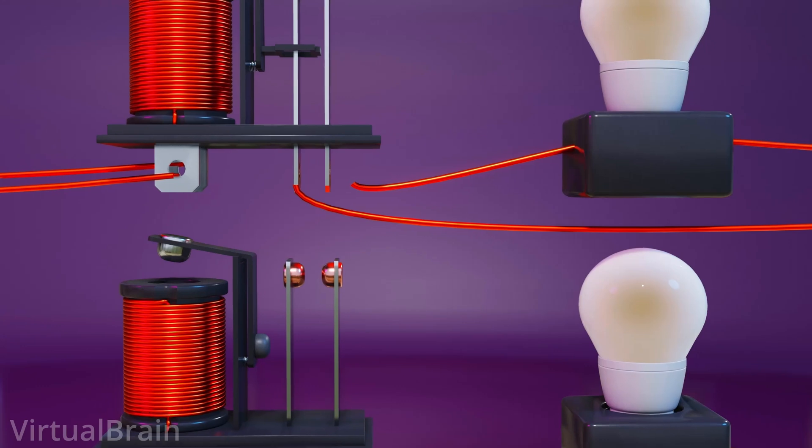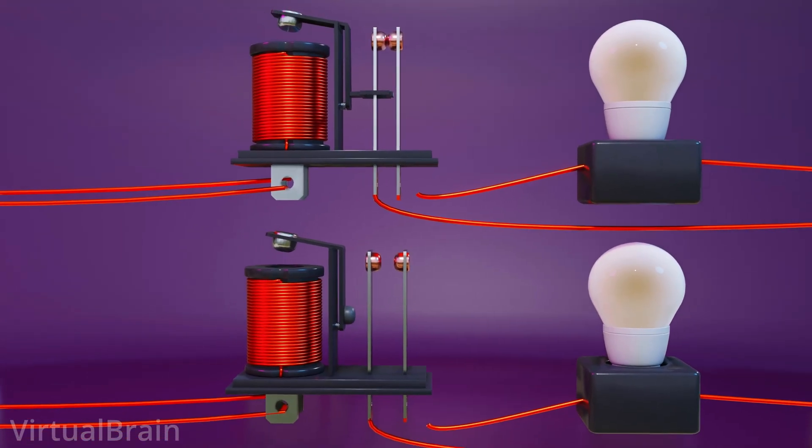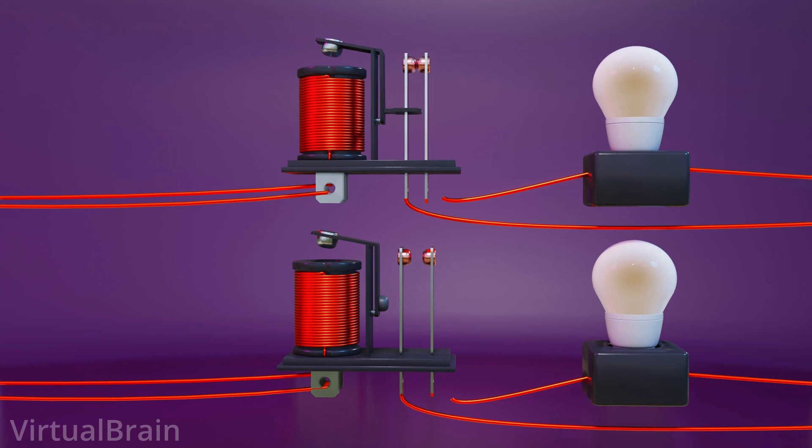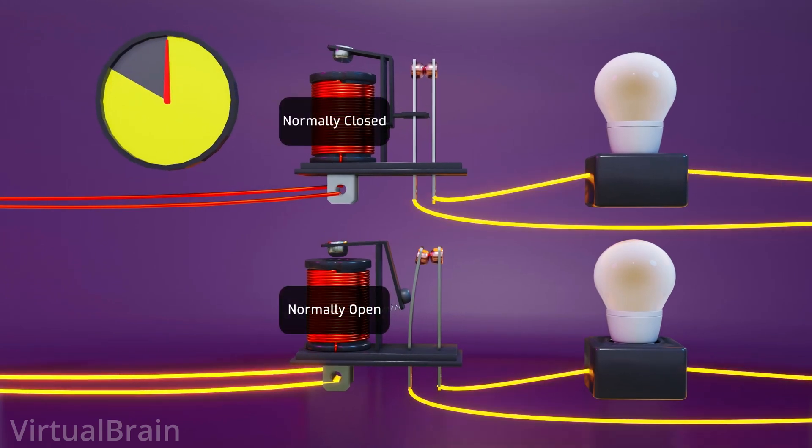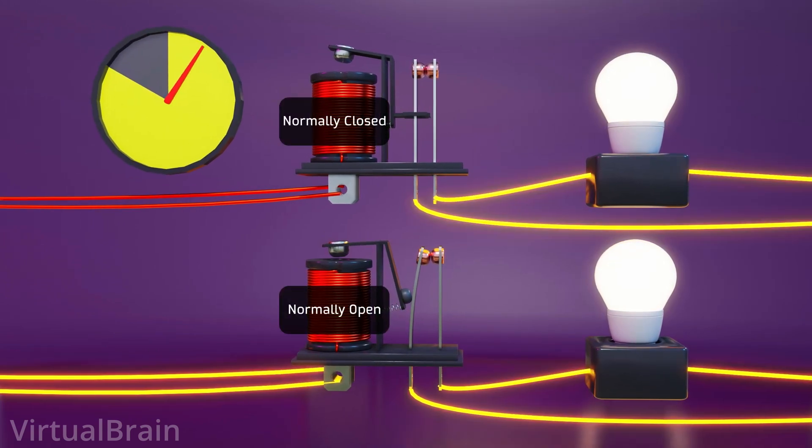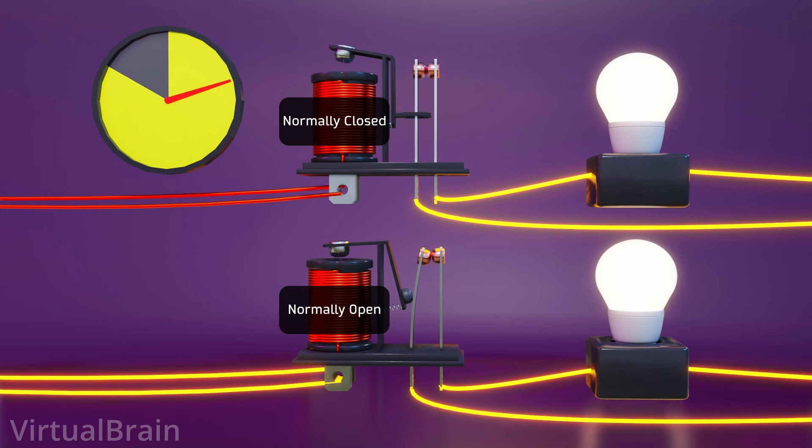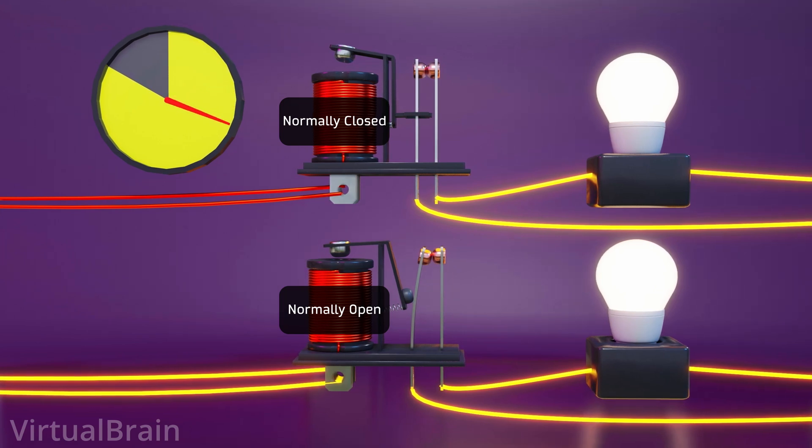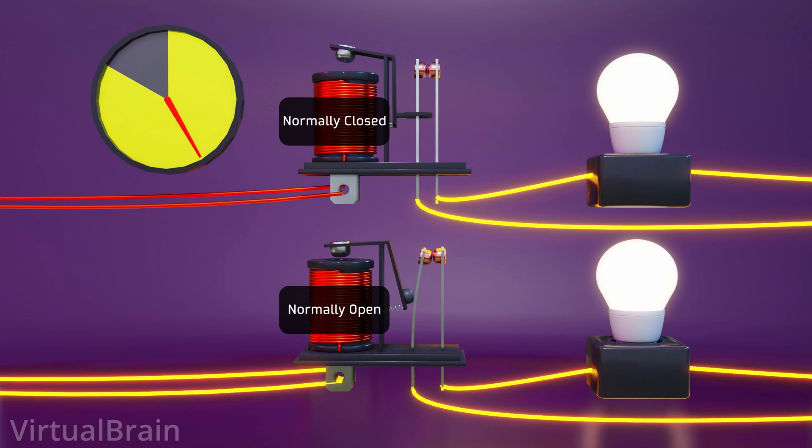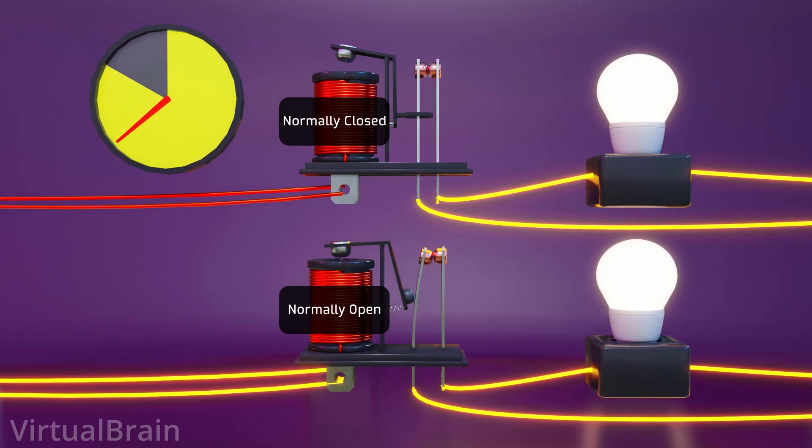In addition to this, in other contexts, the choice between a normally open or normally closed relay can have energy implications. For example, if we want to control a lamp that we want to keep on for 20 hours and off for 4 hours, then it would be better to use a normally closed relay, as we would only need to keep the relay energized for 4 hours, as opposed to a normally open relay, which would need to be energized for 20 hours.